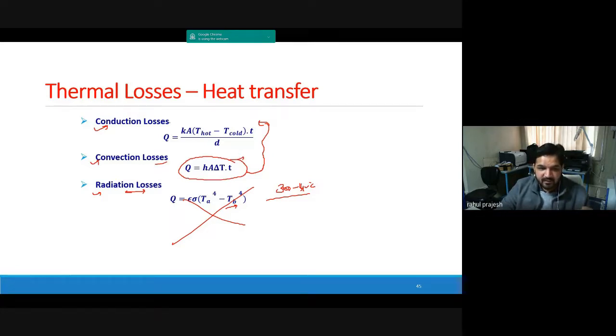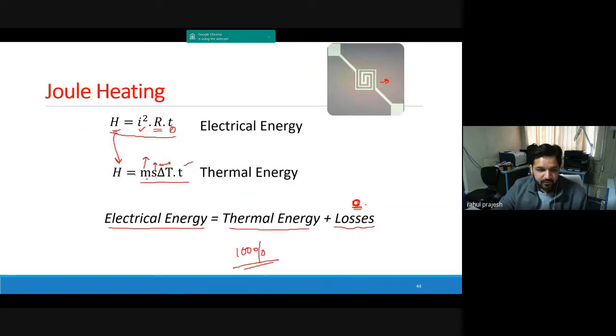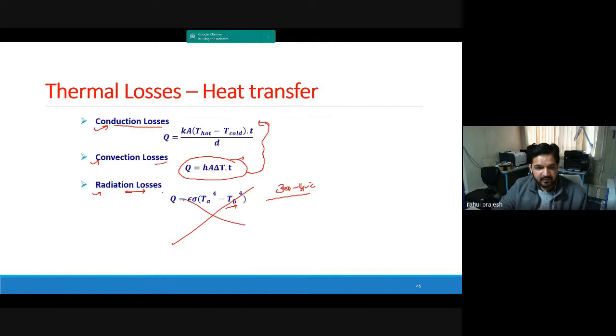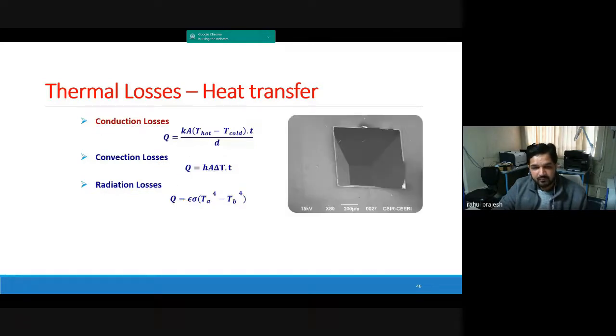If you can control something in the sensor, that is conduction losses. Conduction losses are basically the mass which is in contact. So you need to reduce this thermal mass - that's where you can do something about conduction losses. That's the reason we remove material from the back to reduce them.